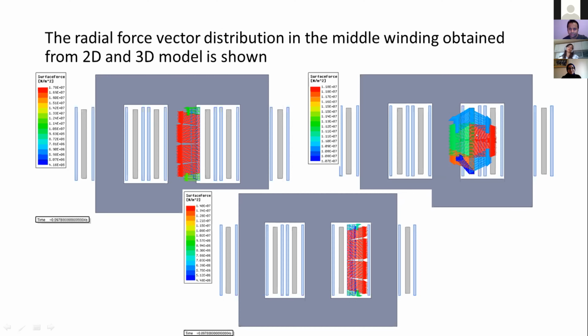And the high voltage winding has a direction of radial force to both sides, but its magnitude is higher to the tank side, and also the radial forces have greater value in the middle area of the windings, because in these areas the axial flux is higher.